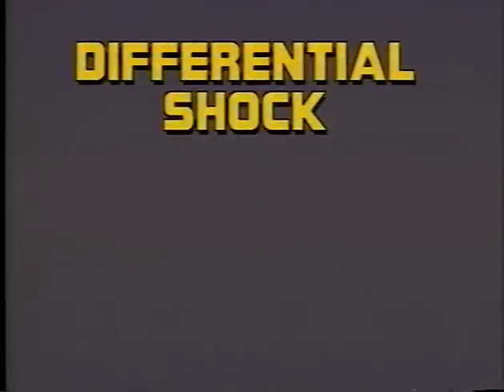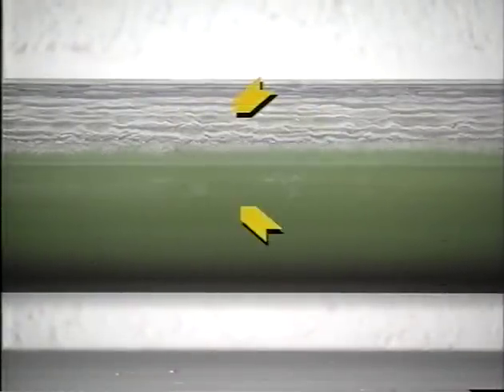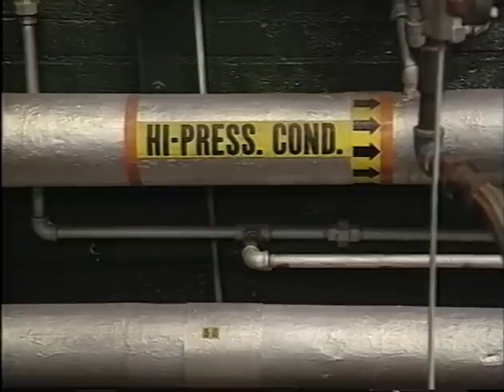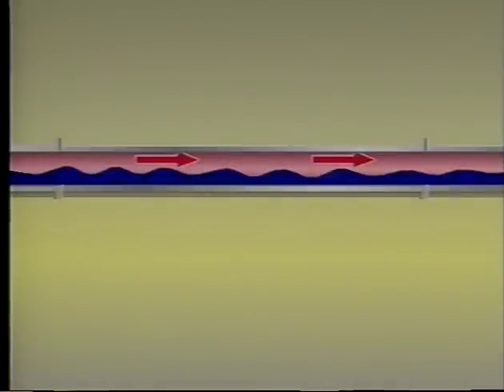Differential shock, like thermal shock, occurs in biphase systems. Differential shock can occur whenever steam and condensate flow in the same line, but at different velocities, such as in high-pressure condensate return lines. In biphase systems, the velocity of the steam is often ten times the velocity of the liquid.